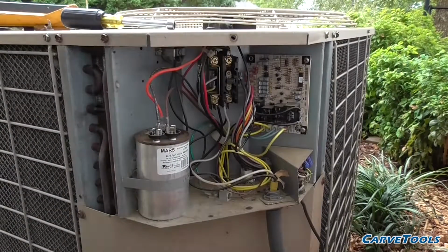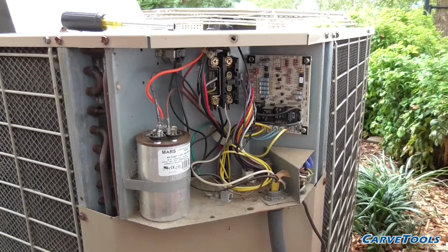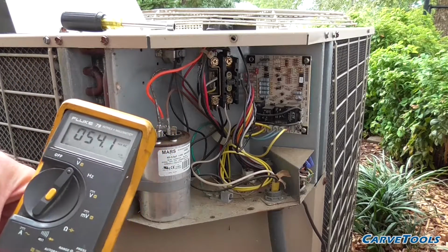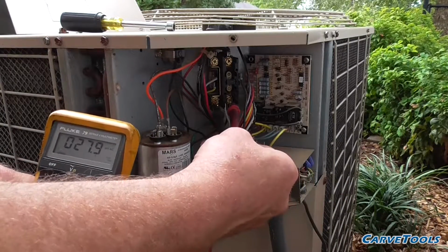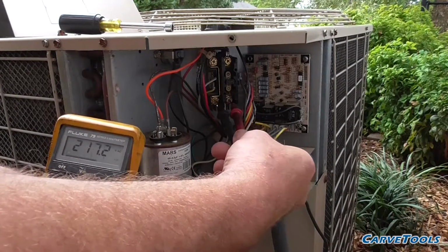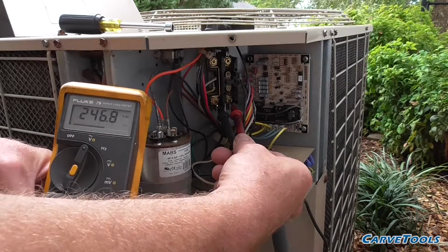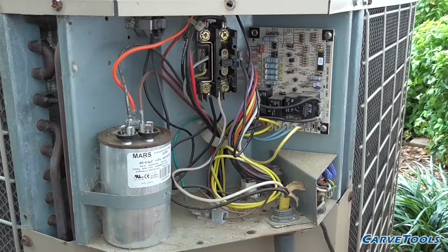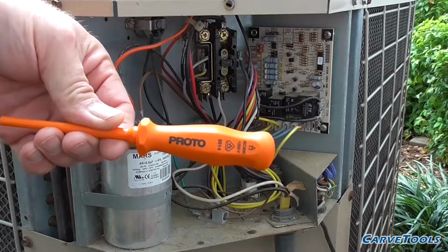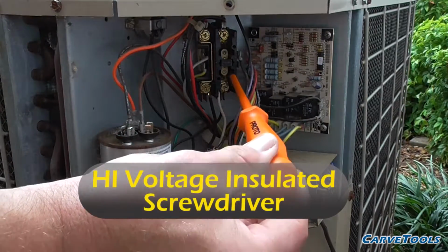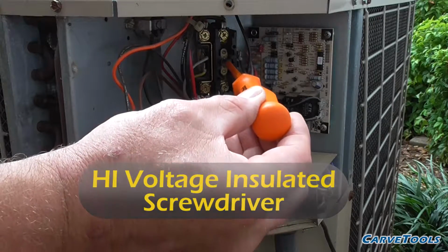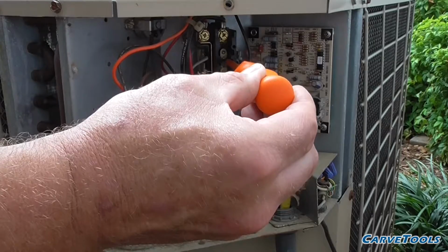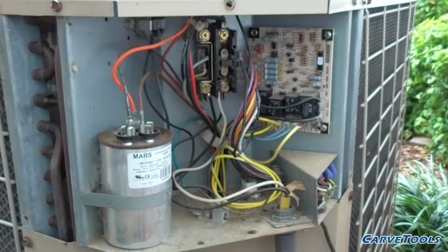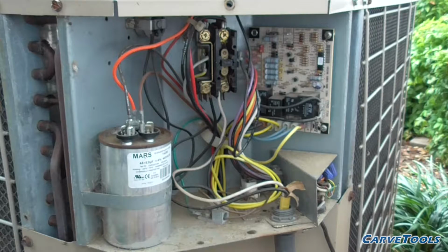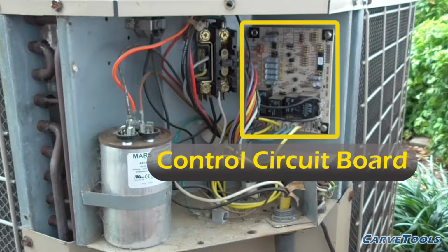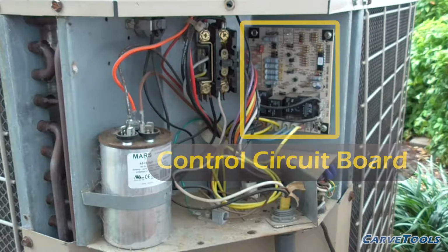Removing the panel here on the outside unit, I will check for voltage. And it reads 246 volts AC, so that's a good sign. Hopefully the lightning did not damage the compressor, and a quick check for that is to momentarily press in the contactor with an insulated screwdriver. And there it goes. That's a great sign. The compressor and fan will run, so the outside unit is likely okay. But I really have no idea if the electronic control board was damaged at this point.